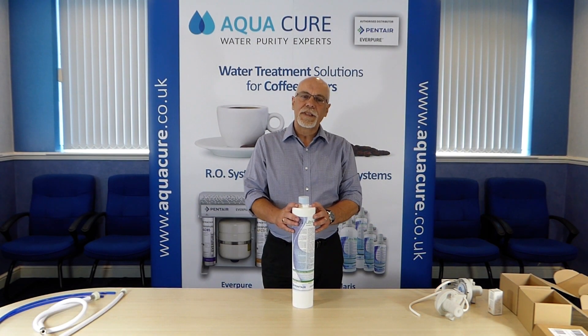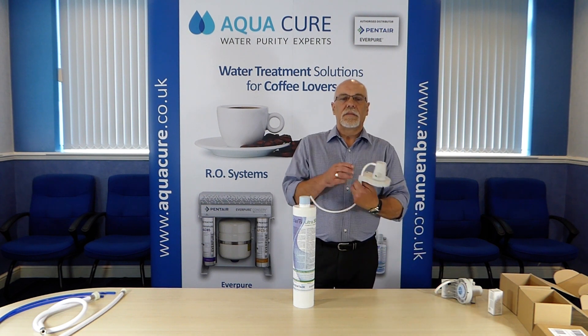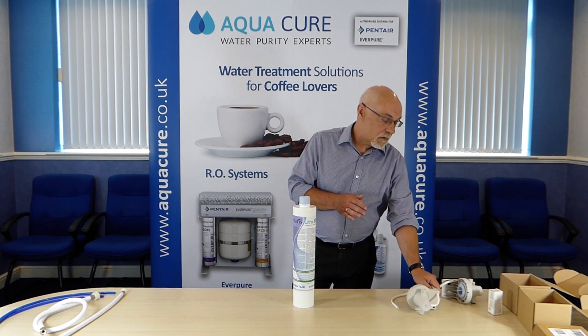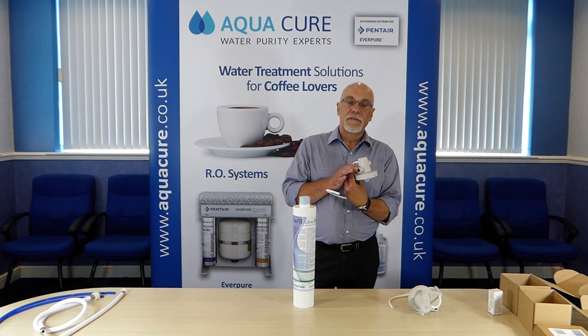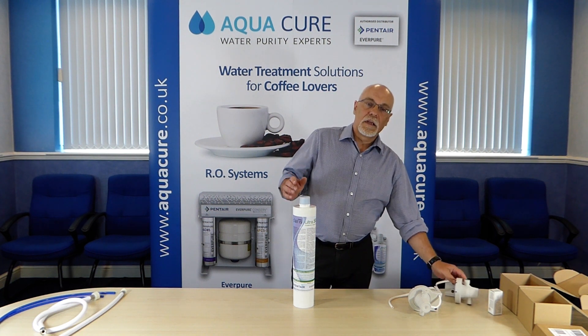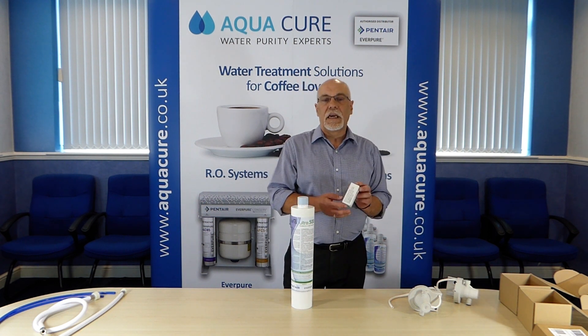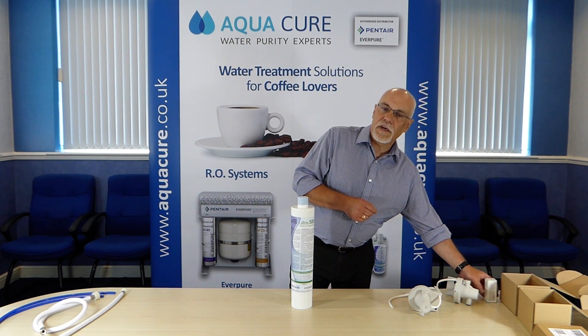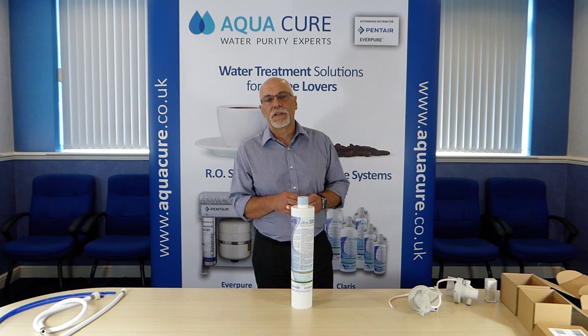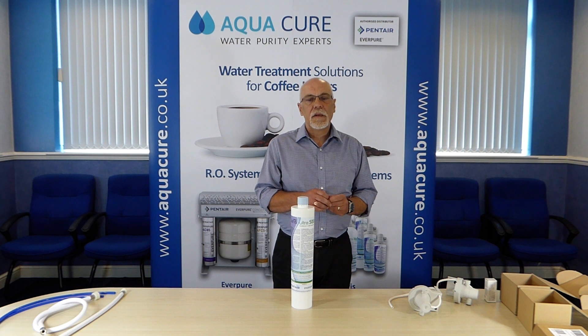The system comprises of a Claris filter head with a three-eighths male connection or a three-eighths push fit connection, depending on what you specify. It comes also with a Claris Ultra filter cartridge and a hardness test kit. Claris Ultra cartridges range in capacity from 1,700 litres for the Ultra 170 cartridge to 20,000 litres for the Ultra 2000, depending on your feedwater ppm and application.